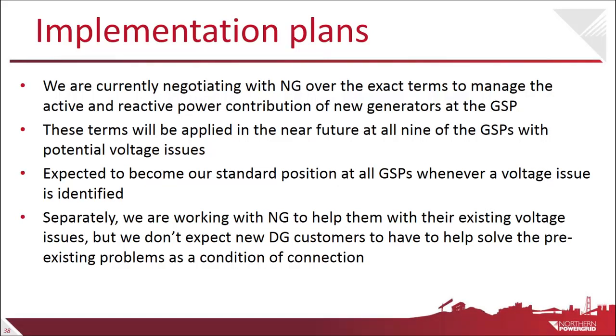There's a couple of things in G99 that are different to G59. G99 requires generators to have the capability to do reactive power at 0.95 lead to 0.95 lag, or even 0.92 lead to lag, depending on the size of your generator. There's also a requirement to have a signal from Northern Powergrid to the generator to reduce their output, so it's partially covered. We've always required generators to run at particular power factors, or given them a range, so I don't think G99 quite does it, but the capability is there in G99 - it's a case of putting appropriate control systems against that.